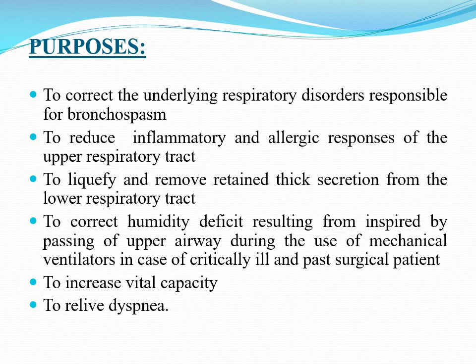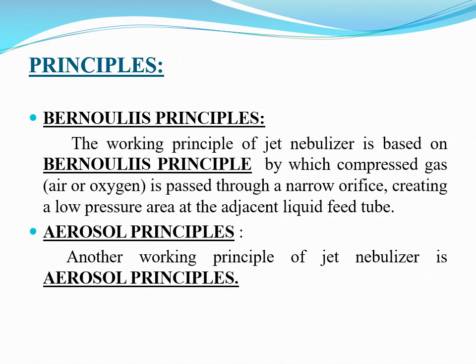Nebulization machine works on two principles: Bernoulli's principle and the aerosol principle. First, Bernoulli's principle. The working principle of jet nebulizer is based on Bernoulli's principle, by which compressed gas is passed through a narrow orifice, creating a low pressure area at the adjacent liquid feed tube. Second, aerosol principle. Another working principle of the jet nebulizer is aerosol principle.